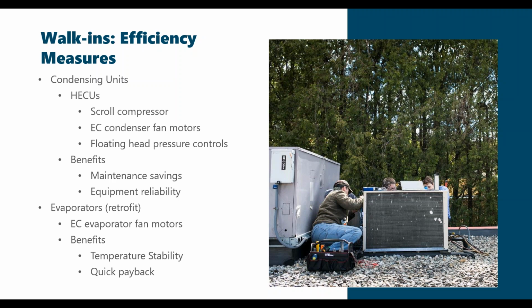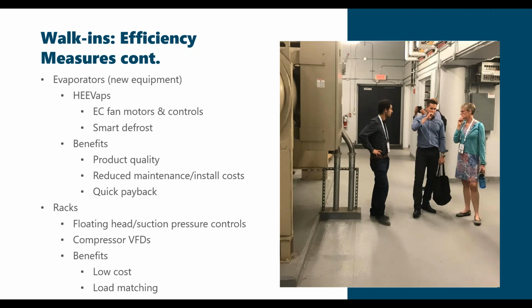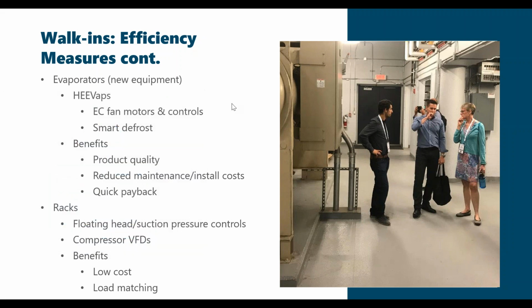And now if we go to the next slide, thank you. We can also then do a full evaporator upgrade. So this is the kind of new equipment side and this high efficiency evaporators. And as we kind of coined it, the HEVAPs. And this is kind of that same package system as we saw with the high efficiency condensing units, where you've got modulating fan motors, you have controls to adjust the speed of those fan motors, and then you have intelligent defrost systems that work on demand. And so that system, again, is designed to work together so it's inherently efficient, and it has then an integral electronic expansion valve in order to do that smart defrost.